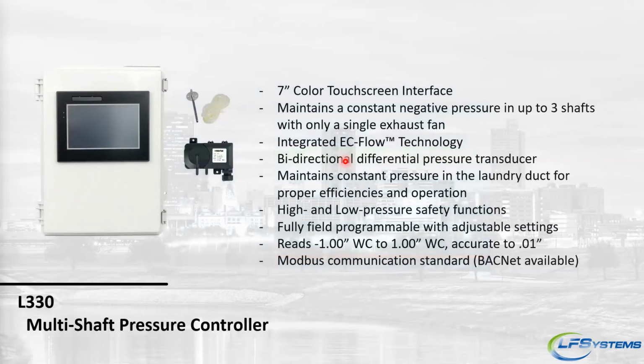A few years back, we started getting requests for combining shafts, and what I mean by that is taking, especially on bathroom exhaust, where you're running 50 to 60 CFM per bathroom, and there's maybe 6 or 8 floors to that building. You're only talking 400 to 800 CFM if you double it up. There's just a lot of really small fans up on the top of the roof. So we started looking at code of how you can basically combine shafts into a single fan.